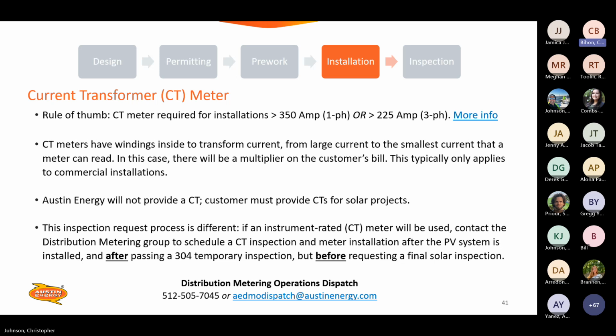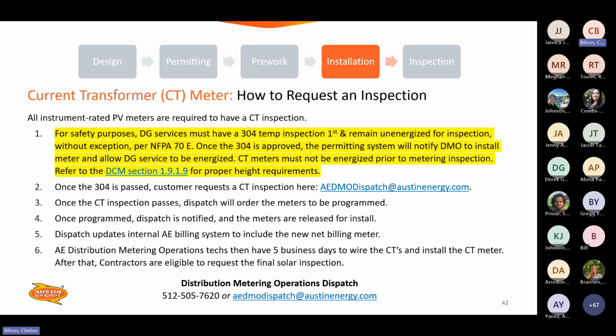Austin Energy will not provide the CTs. The customer must provide CTs for solar projects. The inspection process is different. If an instrument-rated CT meter will be used, contact the distribution metering group to schedule CT inspection and meter installation after the PV system is installed and after passing a 304 temporary inspection, but before requesting a final solar inspection. This is relatively newish information, which I think the next slide will make a little clearer. All right.